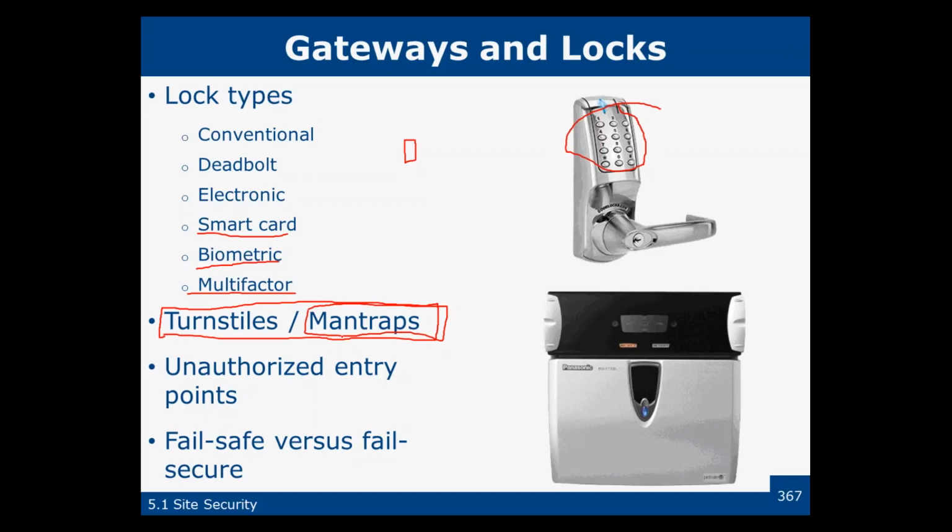We've got fail-safe and fail-secure locks. A fail-safe lock fails open. A fail-secure lock fails locked. If you're using fail-secure locks on doors, they can only fail secure in one direction. You have to be able to get out. You can't stop the egress. The problem with the fail-safe locks is they now have opened everything. So you can have one of these two types of locks.